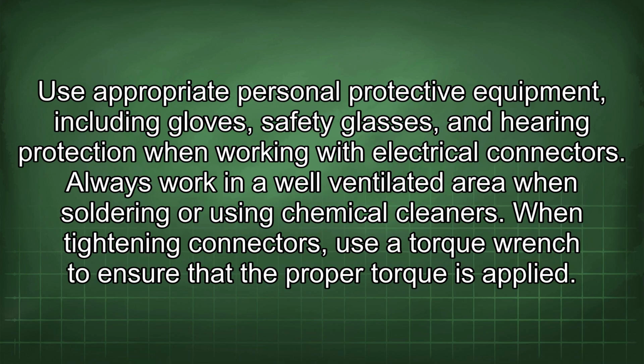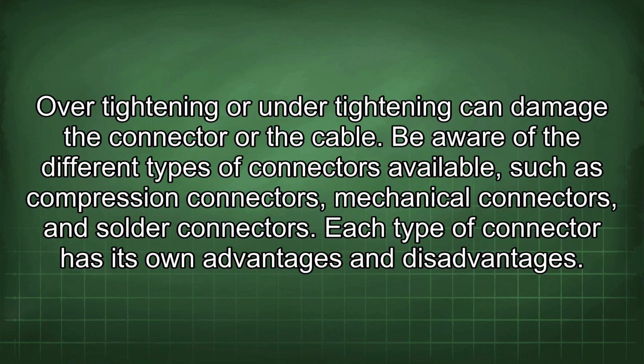Use appropriate personal protective equipment, including gloves, safety glasses, and hearing protection when working with electrical connectors. Always work in a well-ventilated area when soldering or using chemical cleaners. When tightening connectors, use a torque wrench to ensure that the proper torque is applied. Over-tightening or under-tightening can damage the connector or the cable. Be aware of the different types of connectors available, such as compression connectors, mechanical connectors, and solder connectors. Each type of connector has its own advantages and disadvantages.